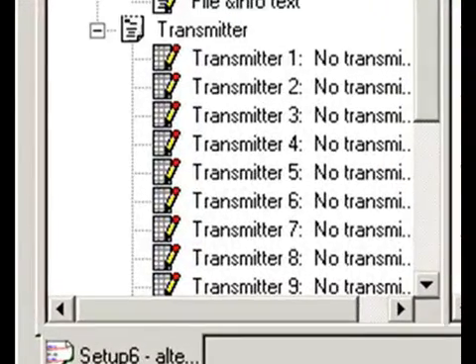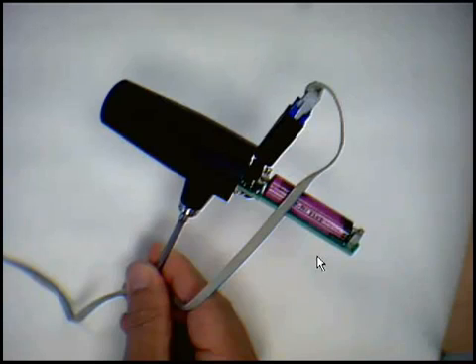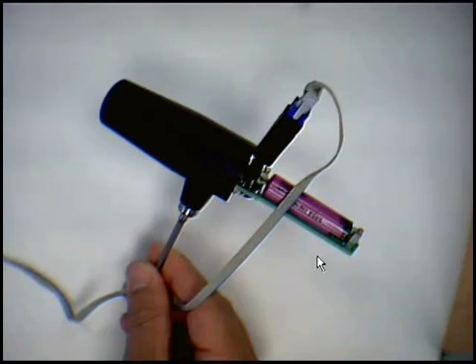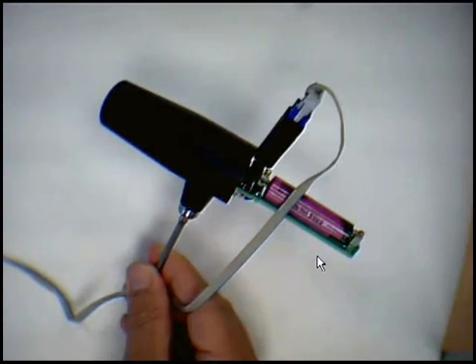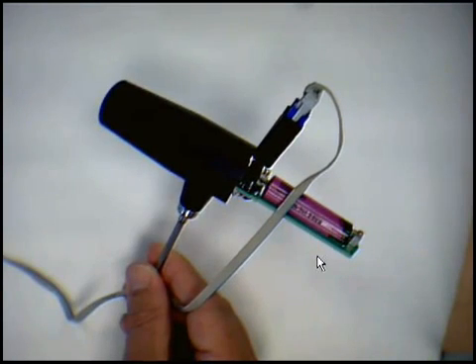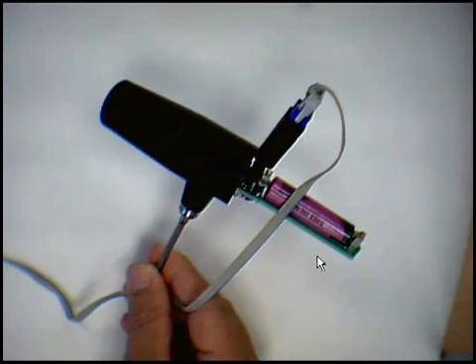Both transmitter units transmit the measuring value to the receiver every 10 seconds. In most cases it is not necessary to change the adjustments for the transmitters. However, if the configuration shall be modified, the PC interface must be connected to the first transmitter unit. In our example, this unit has the ID 768.